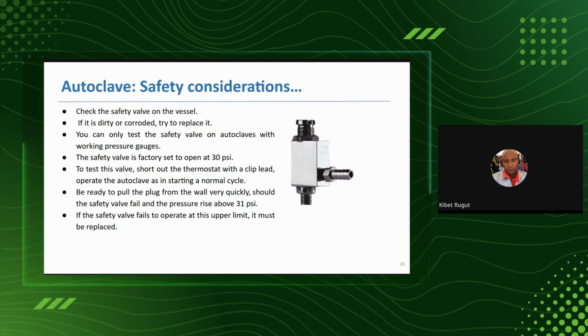Don't try to test it using just your own expectation. They are normally set, for example, to 30 psi. If you pull the plug and there is steam in the jacket, you will hear the steam going out with a bang. So it is good to know what you are doing at that time. Maybe you're just checking the operation and the safety of the system. So you don't do it if it is not during a scheduled maintenance.